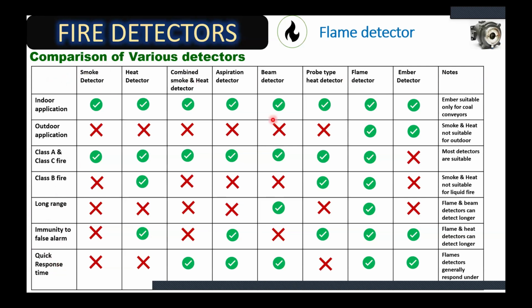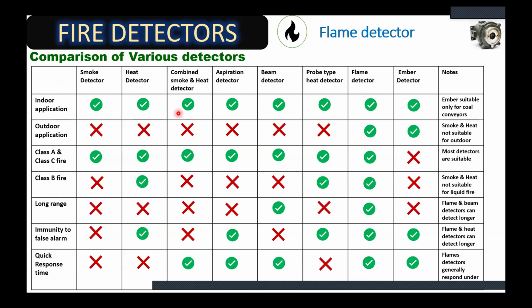And on the first row, we have different types of detectors, which are the smoke detector, heat detector, combination detectors, aspiration detectors, beam detectors, probe type heat detectors, flame detectors, ember detectors. Right. So as you can see, I'm not going to elaborate this table in detail, but each type of detector has its pros and cons, wherein the flame detector has a unique advantage wherein it can be used indoor, outdoor, for class A, class B, class C fires, with long range detection capability, immunity to false alarms, and a quicker response time, which makes the flame detector a detector with enhanced fire detection capability.